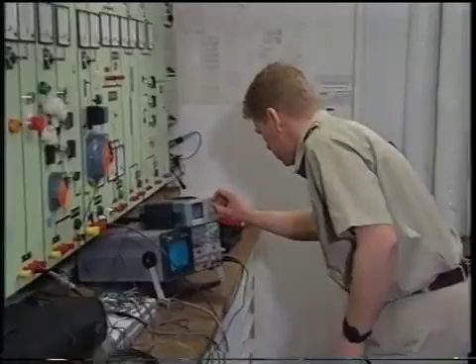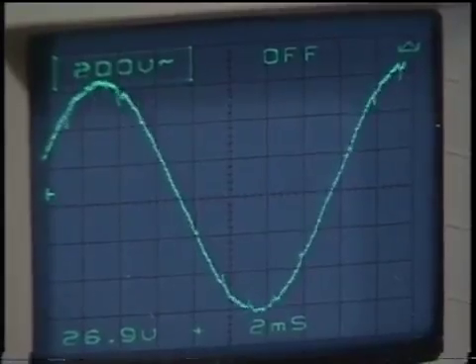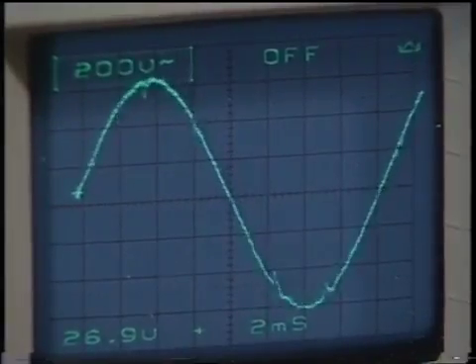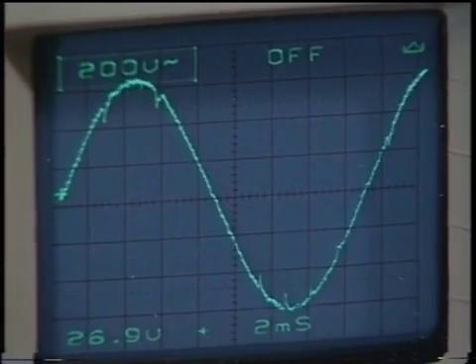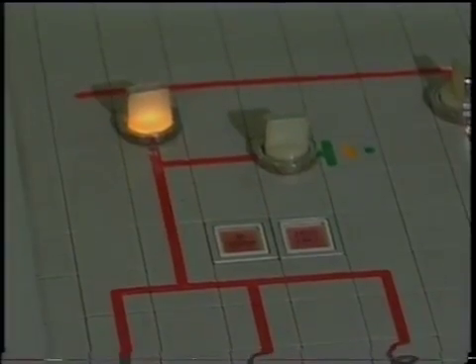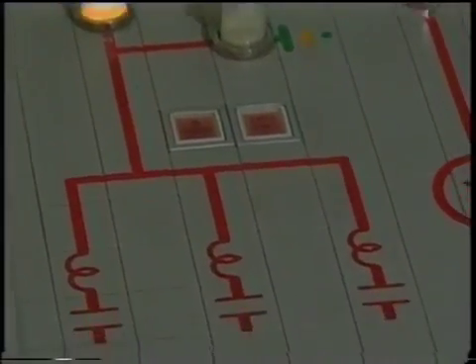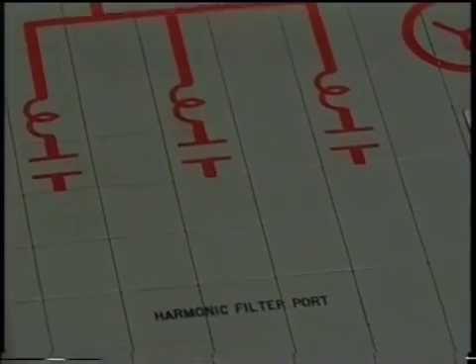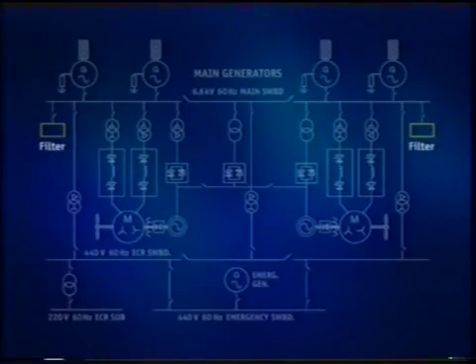Here we see the AC supply voltage has harmonic disturbance, showing as small spikes on the sinusoidal waveform. This is because the propulsion is running without harmonic filters, which have tripped out due to a fault. The harmonic filters are circuits with very low impedances which are tuned to the troublesome harmonic frequencies. The filter action is to absorb unwanted harmonic currents caused by converter switching.